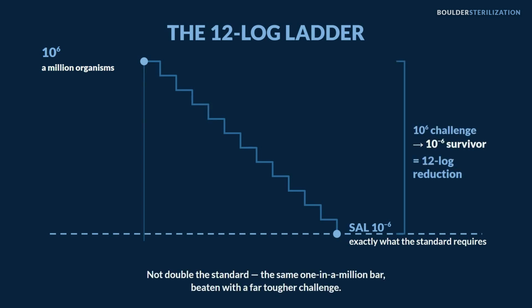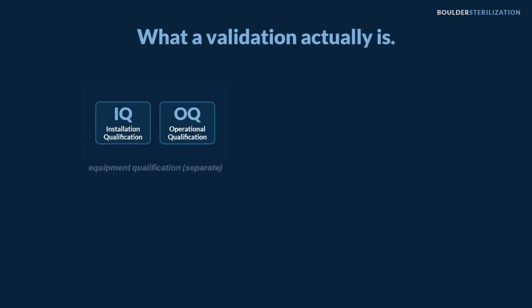is where overkill comes from. But let's be precise about what we're certifying. The sterility assurance level we deliver is exactly what the standard requires, 10 to the -6. We're not doubling the standard. We're proving we hit that same 1 in a million bar even when the thing we're trying to kill is far larger and far tougher than your real product. That's the margin.